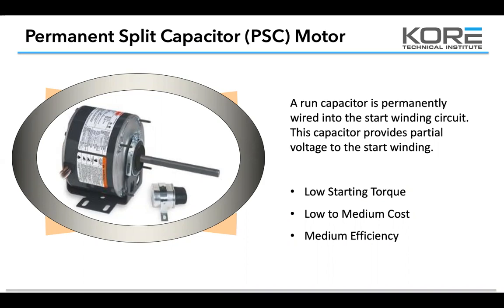Permanent split capacitor motors, PSC motors, are probably, if not the most common, the second most common motors. If you are an HVAC tech, it'd probably be your most common motor. We still see a lot of shaded pole. And then ECM motors, or EC motors, are taking the place of a lot of the shaded pole stuff. That's where we're getting that high energy efficiency, and because of the low starting torque, we're able to do that. This permanent split capacitor has a little bit more starting torque than a shaded pole most of the time, but there's not a whole lot of load you can throw on there. So a run capacitor is permanently wired into the start winding circuit. This capacitor provides a partial voltage to the start winding. So it has a low starting torque, it's a low to medium cost, and it's a medium efficiency.